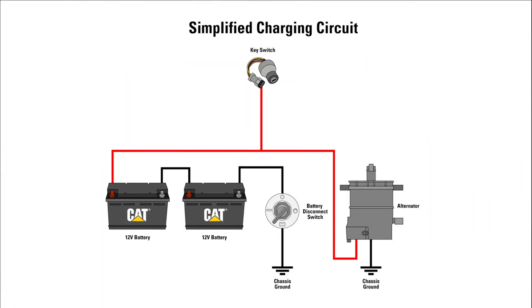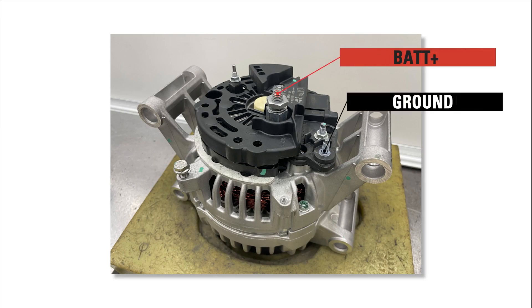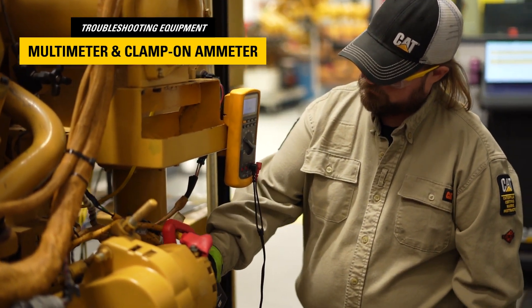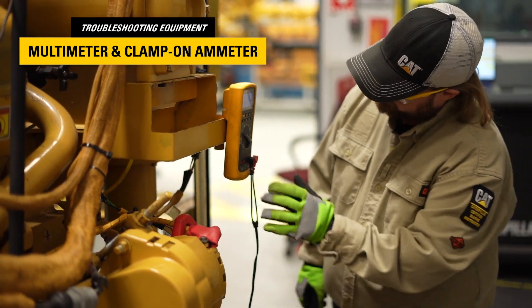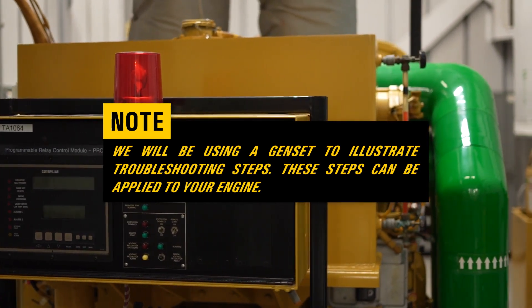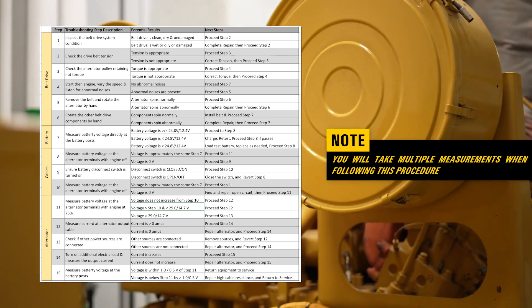A simplified charging circuit is displayed here. The terminals for testing are highlighted as shown and will be used throughout this video. The terminal in red is the battery plus terminal, and the terminal in black is the ground terminal. Most alternators will have these terminals labeled. If you are unsure, please consult your local Caterpillar dealer for assistance. To complete the troubleshooting steps, you will need a multimeter and a clamp-on ammeter. We will use a CAT genset to illustrate the troubleshooting steps. These same basic steps can be applied to your engine. You will take multiple measurements when following this procedure, which can be recorded in this chart.